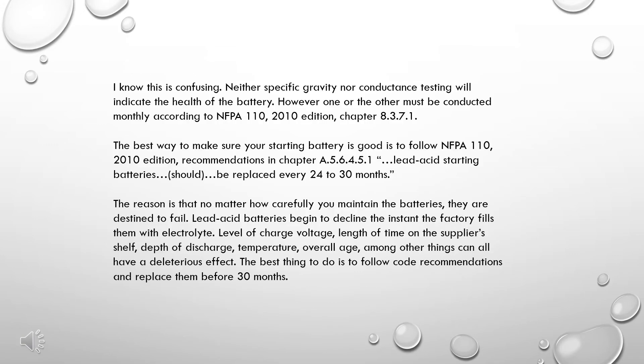I know this is confusing. Neither specific gravity nor conductance testing will indicate the health of the battery. However, one or the other must be conducted monthly according to NFPA 110, 2010 edition, Chapter 8.3.7.1. The best way to make sure your starting battery is good is to follow NFPA 110, 2010 edition recommendations in Chapter A.5.6.4.5.1.